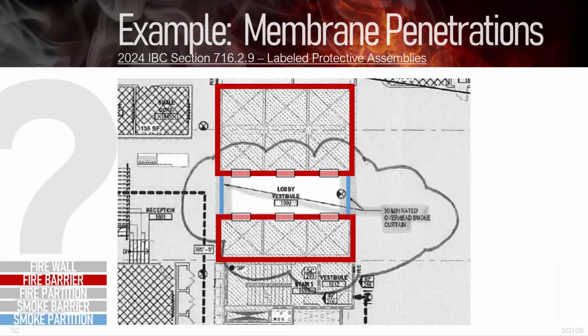To get around that whole issue with the swing doors that we were looking at in the last one, a little benefit we have on this drawing is that they have shown us where the exit signs are. So this is what we know our exit path to be. Are the exit signs? We're not going through that elevator lobby. We're going either direction. Now, if they made a mistake and had to egress through that elevator lobby, they made another mistake by not putting an egress or an exit door above that door. However, they did that on the other end of the lobby, so I doubt that's the case. And I know this architectural firm, they don't make elemental mistakes like that.